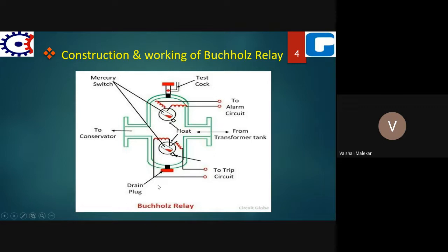Now here, this Buchholz relay relies on the fact that an electrical fault inside the transformer tank is accompanied by generation of gas. Whenever a fault occurs, heat is produced, and due to the heat, gases are formed. If any minor fault occurs inside the transformer, heat will be produced, obviously due to the fault current. Now if heat is produced, then the transformer oil gets decomposed and gas bubbles are produced.